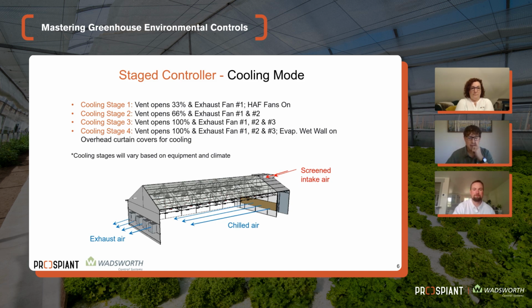Another point, just because we were comparing thermostats a minute ago to the stage control is: if you look at cooling stage 1, we're opening the vent a certain percent and turning on the exhaust fan. Well, when we do that in a control system, the control knows what percent that vent is open before we turn that exhaust fan on. So if it gets really hot really quick, it's not going to just turn the fan on — it's going to wait for that vent to open. And if that was controlled by a thermostat, you might be causing a negative pressure in that house and damaging your structure or damaging that vent from even opening.